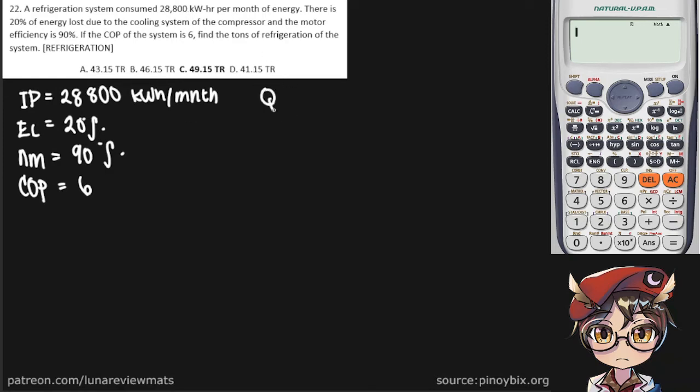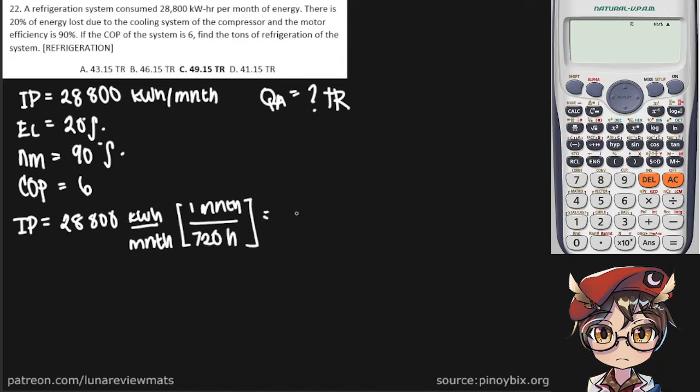In this case is Qa in terms of tons of refrigeration. So first we should convert our indicated power into kilowatts. In a month, there's an average of 720 hours. So we get an indicated power of 40 kilowatts.